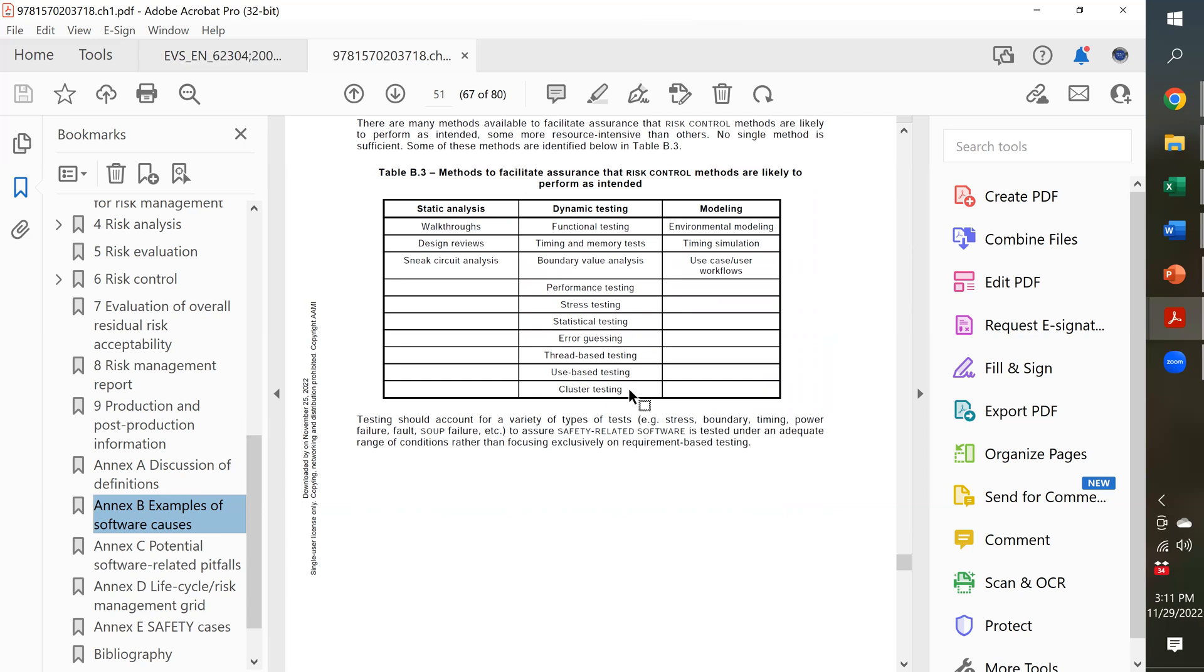You have to put in, for example, a boundary value analysis. You're going to put in numbers that are purposely at the edge or just beyond the edge of a normal range of numbers that you would put in there and see if it gives you an error or not. And does it fail in an unsafe way or does it fail in a safe way?